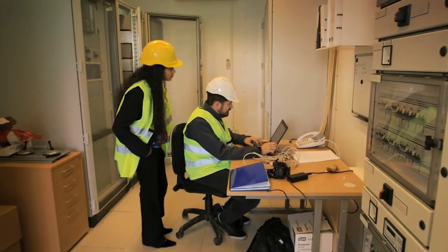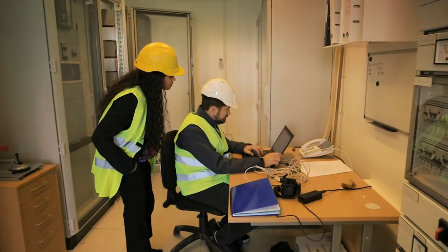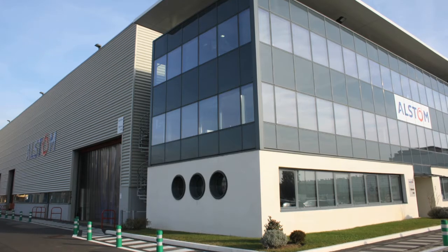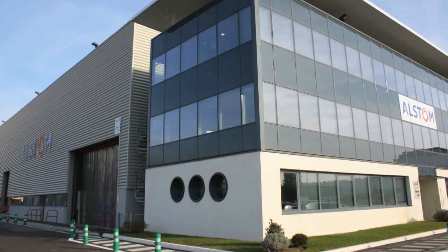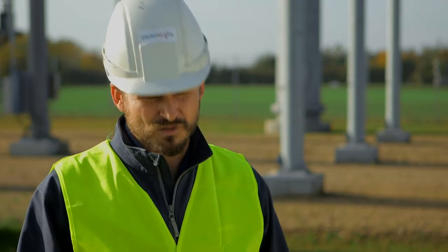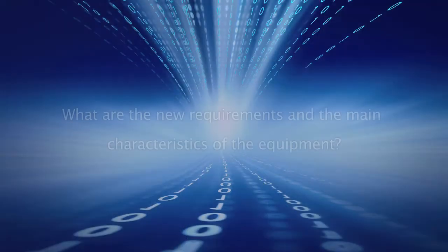Commissioning this system was initiated by the FAT test, the factory acceptance test in Villeurbanne, where we did a full scheme setup of the whole system. We did a one-to-one setup of the whole system and simulated a primary injection. That gave us a very good feel of the full system, because this was new to us. We had to be safe and sure that when we did the installation, we didn't run into any problems that would postpone the installation process.